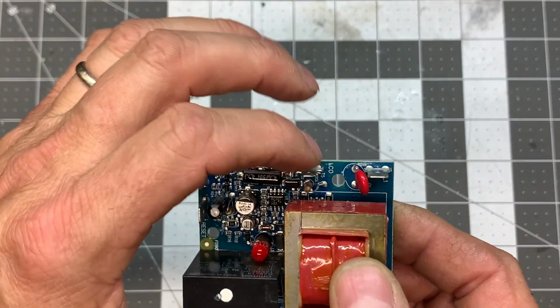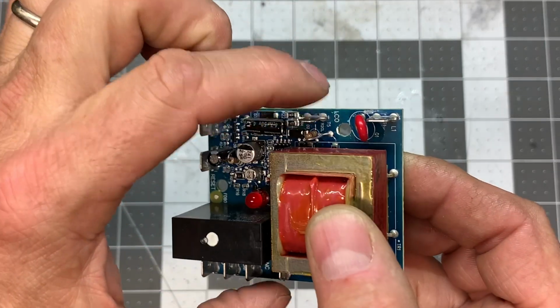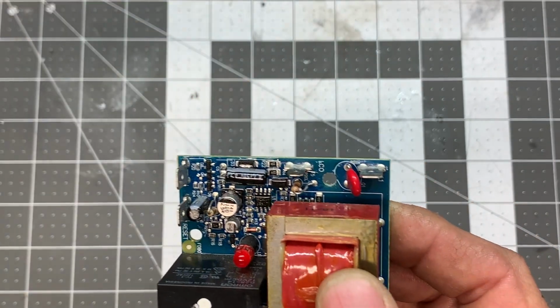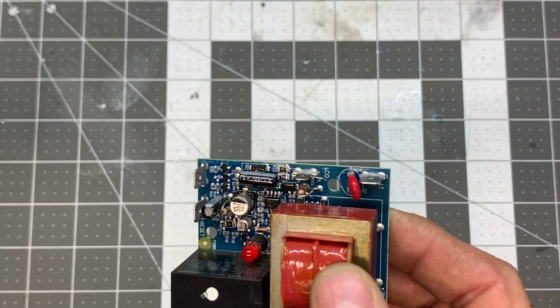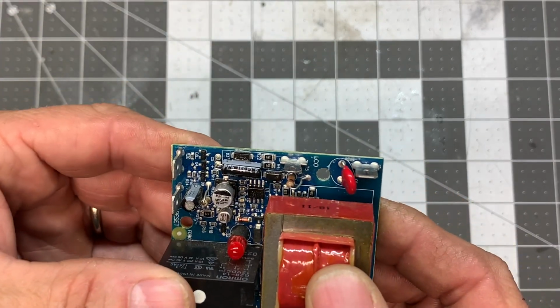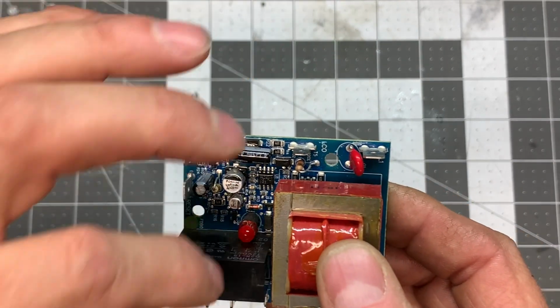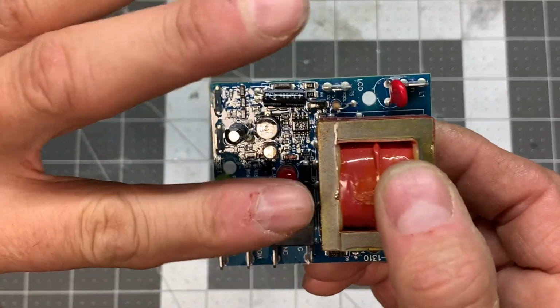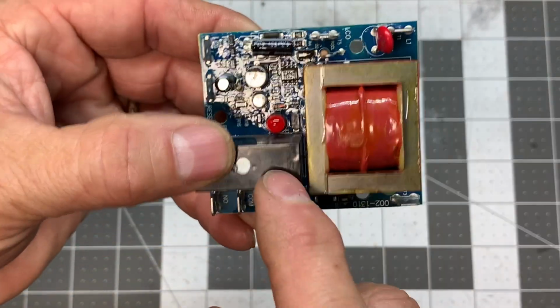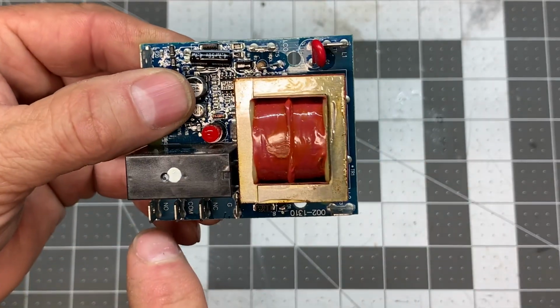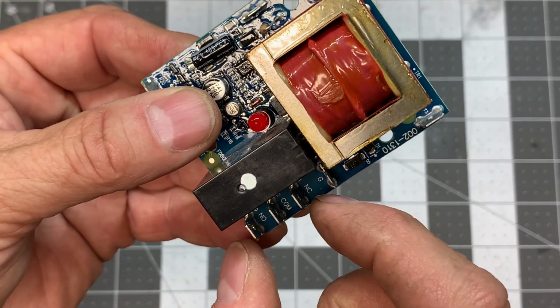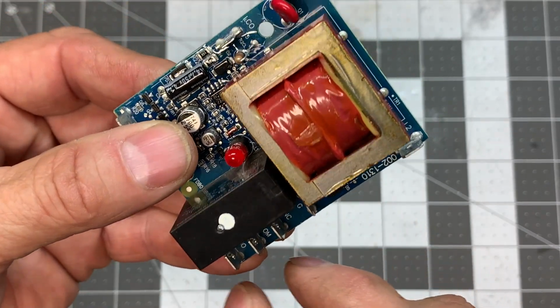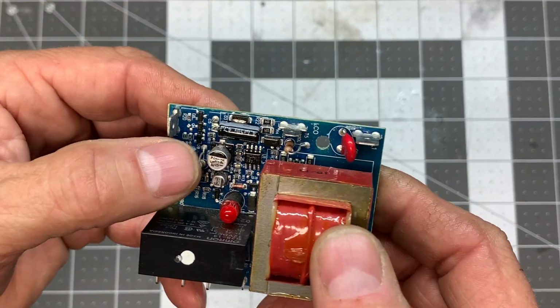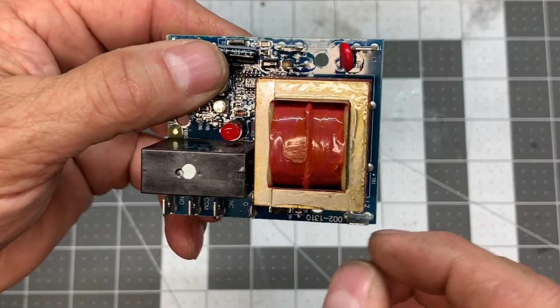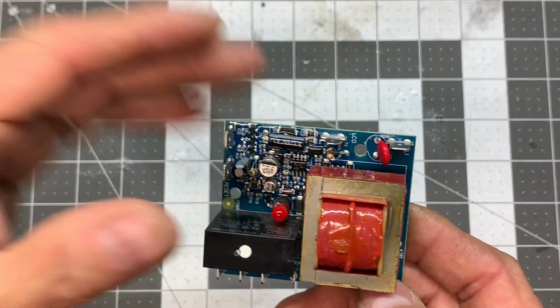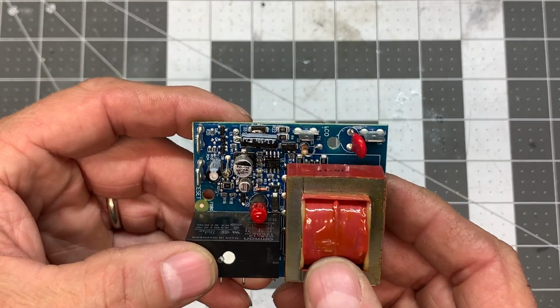So if the resistance is not correct between these two terminals, based on the presence of water touching the tip of the probe, then that turns this circuit, opens this relay. And if this relay is open, because of the normally closed and common terminals, the boiler will not fire. It goes into an alarm condition that the low water cutoff circuit is engaged.